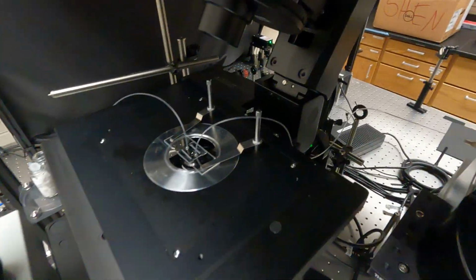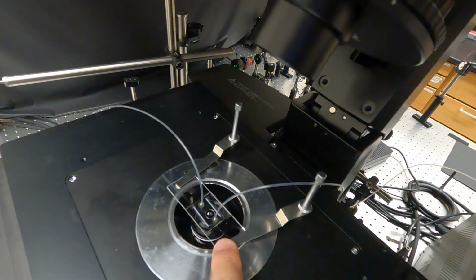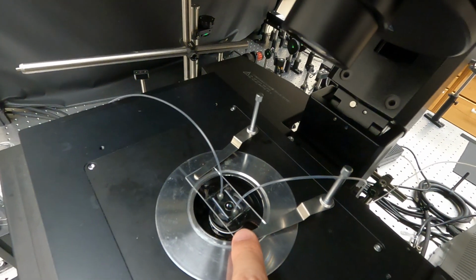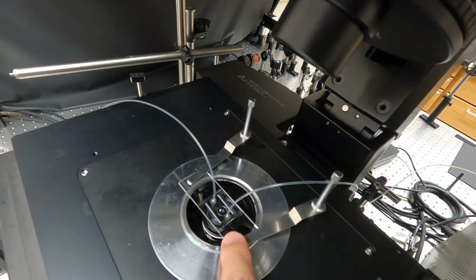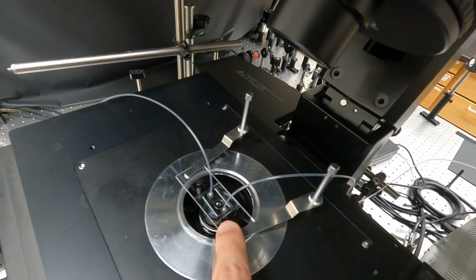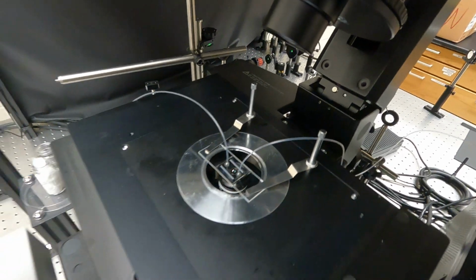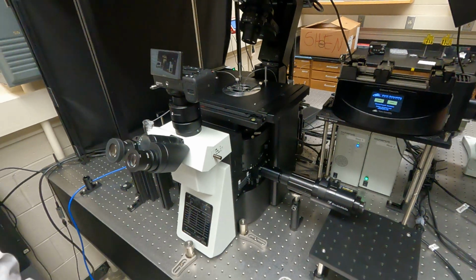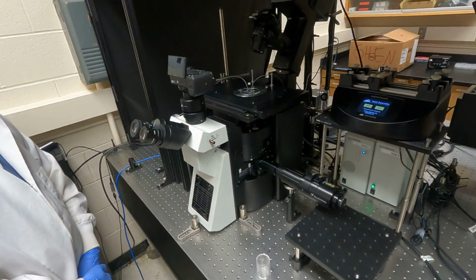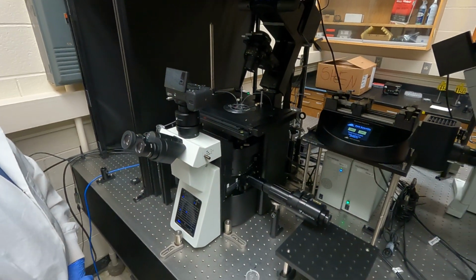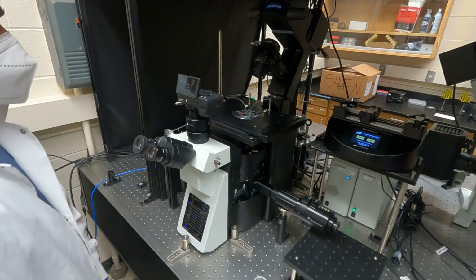And then also, typically when we prepare the flow chamber, we will use epoxy to make the seal. Try to avoid the contact of the objective lens to the epoxy layer, because the objective lens is very delicate. Epoxy can potentially damage the front element of the objective.